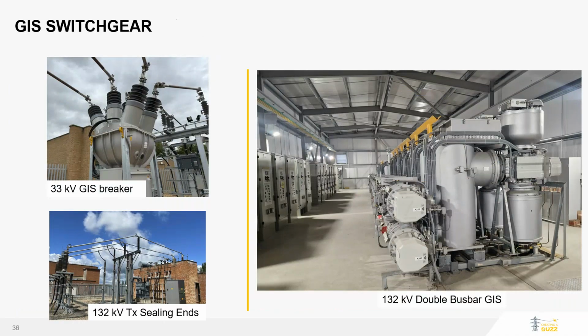Another combined consideration is the cable entry for the equipment. So here we see high-level connections to the 33 kV GIS breaker, which would require additional cable support. The image below is of a 132 kV transformer and its associated cable support. Alternatively, we have an indoor 132 kV double bus bar, which can accommodate bottom entry cable termination utilizing subsurface cable routes.